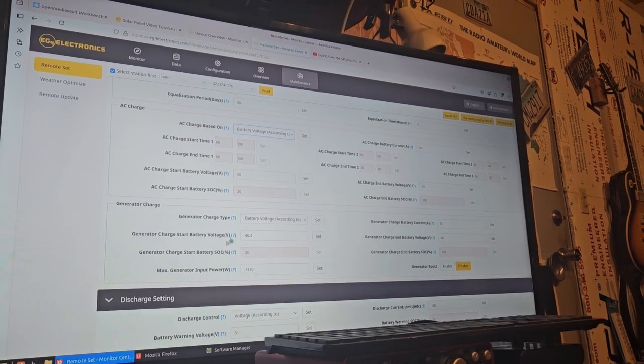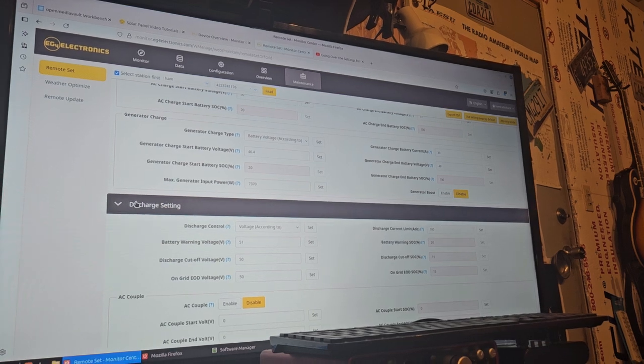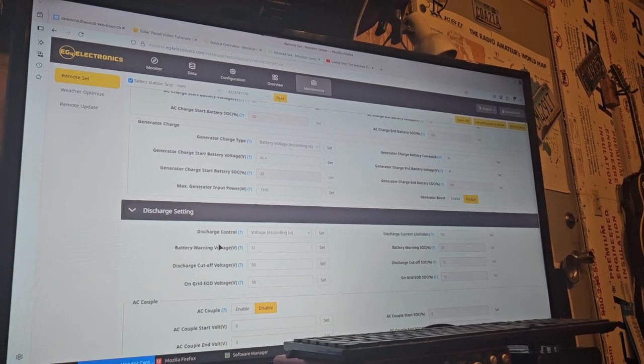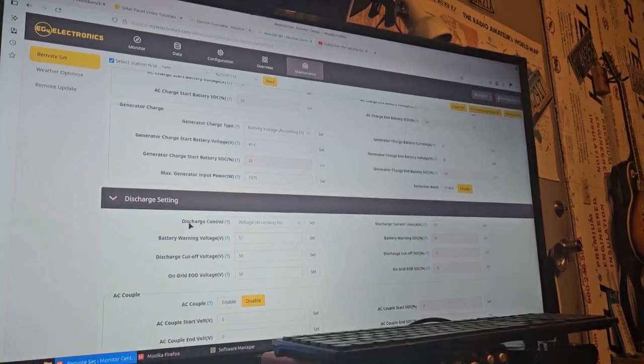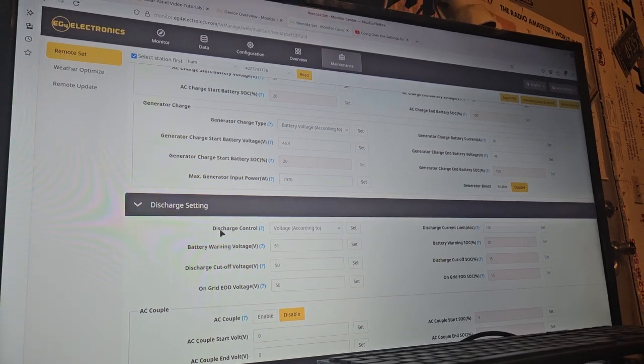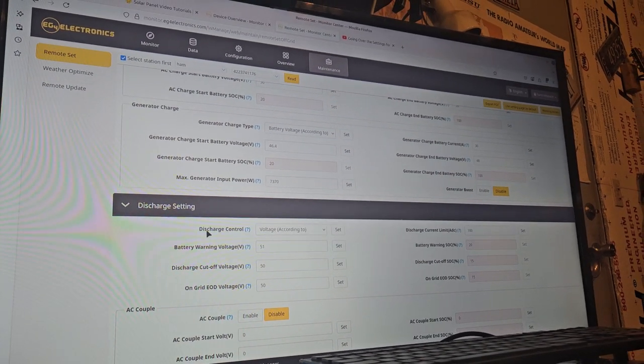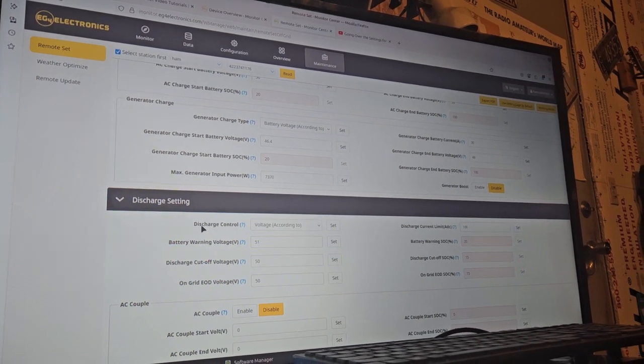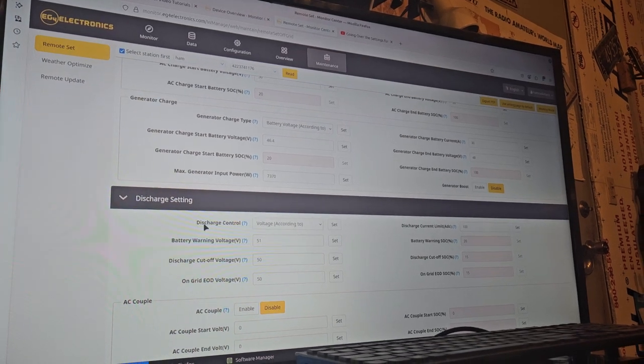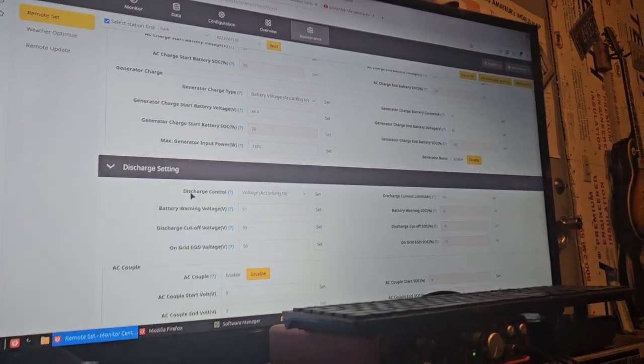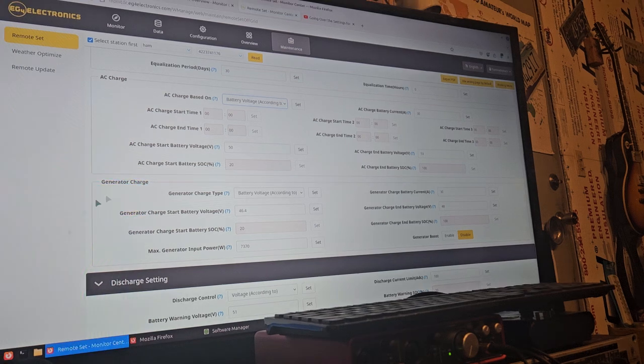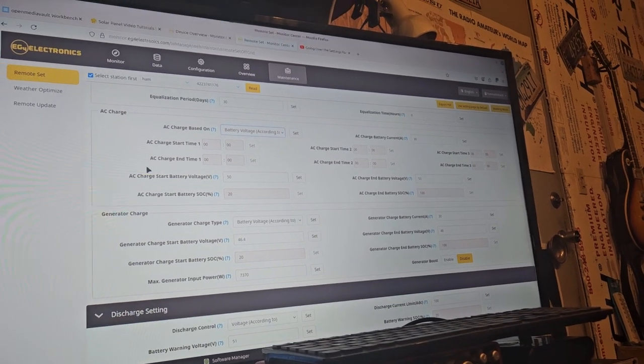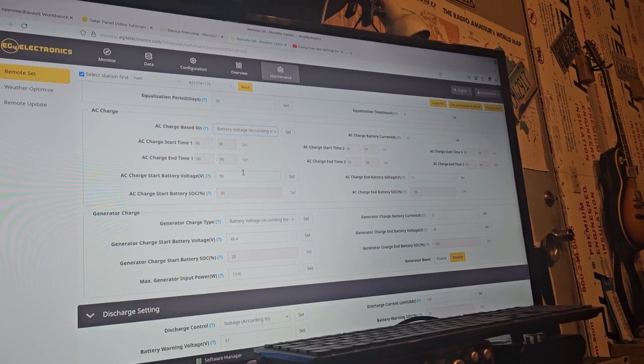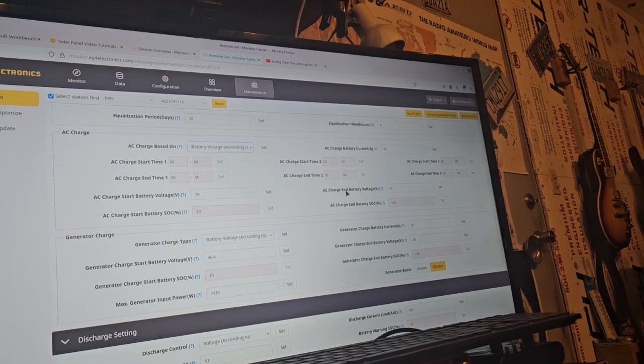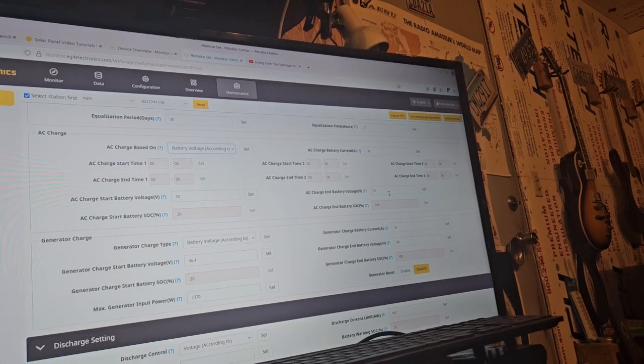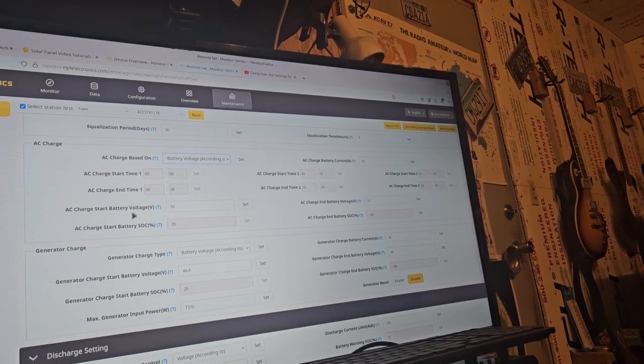Then you have the whole generator setting, which I'm not going to mess with because I don't have a generator. And then your discharge settings — these get a little confusing for me. There's a discharge cutoff voltage and a warning voltage, and the warning voltage has to be higher than the cutoff voltage. Also, if you can't get this thing to charge, make sure your charging voltage is lower than your end battery charging voltage — make sure you catch that if you have one of these.